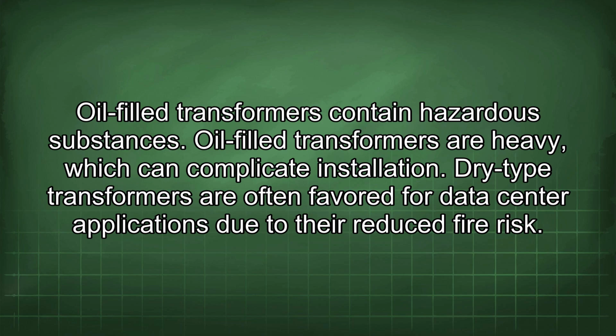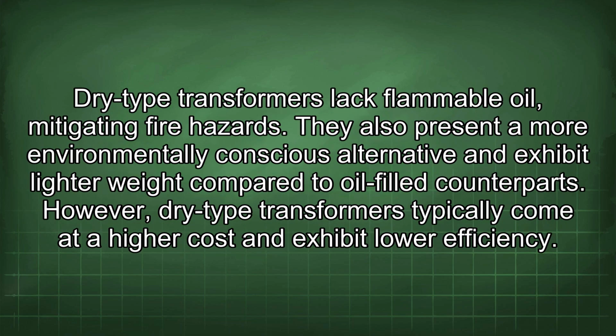Dry-type transformers are often favored for data center applications due to their reduced fire risk. Dry-type transformers lack flammable oil, mitigating fire hazards. They also present a more environmentally conscious alternative and exhibit lighter weight compared to oil-filled counterparts. However, dry-type transformers typically come at a higher cost and exhibit lower efficiency.